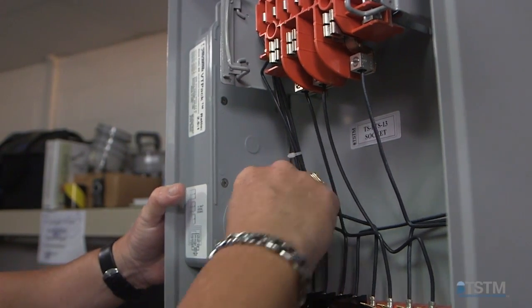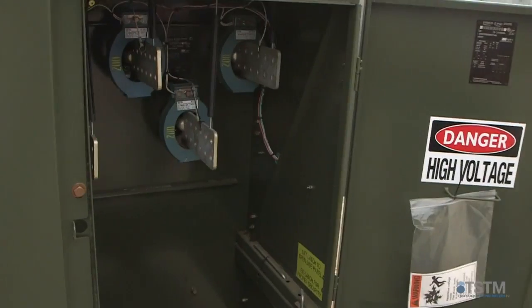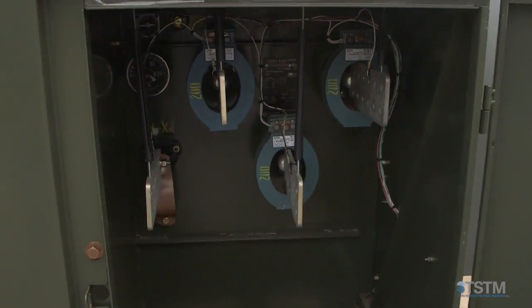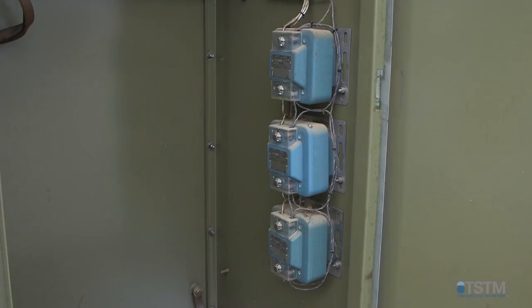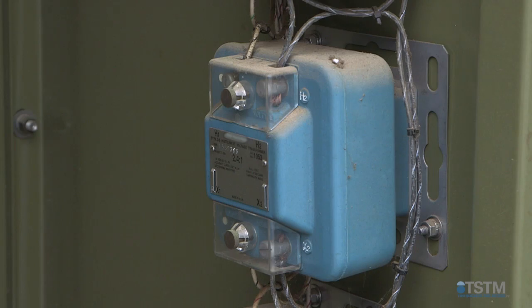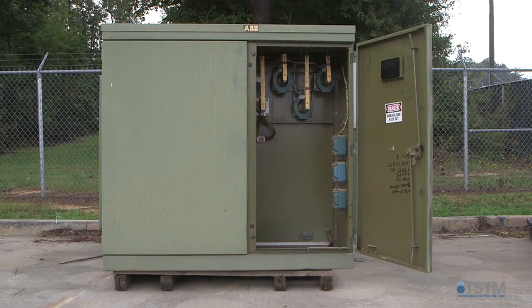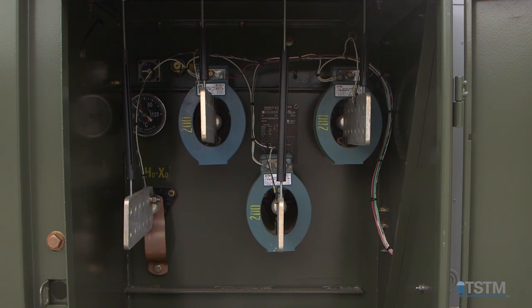If you're working in a 75 kVA pad mount, 277/480, the space isn't there to mount 3 individual VTs. We have to get them in there to reduce that voltage, and we have done it, but you're looking at an additional 2 hours of labor wiring and mounting those VTs, and then they're going to be in the way of the conductors when the line crew personnel get there to run the conductors in the transformer.